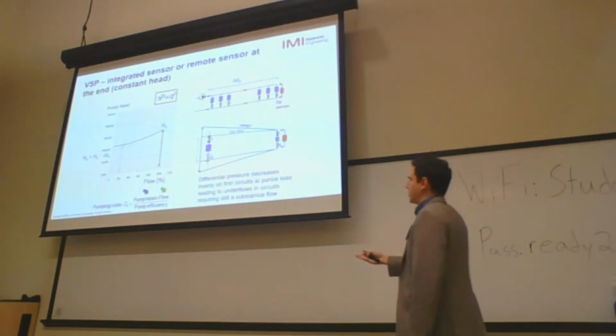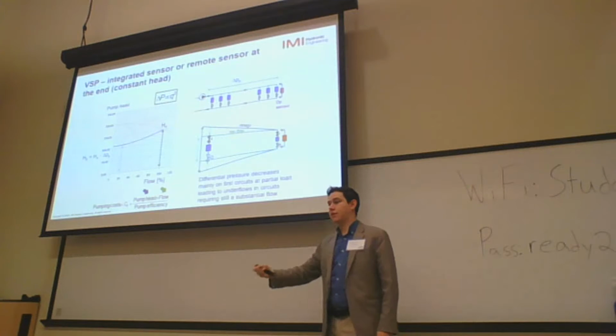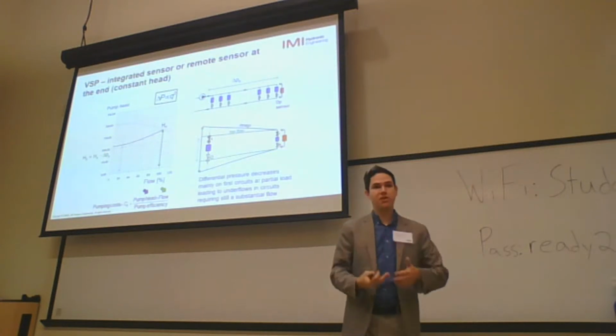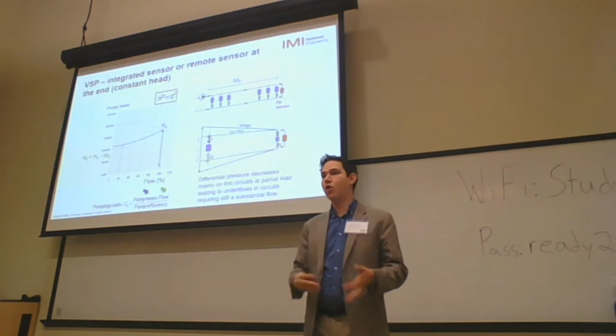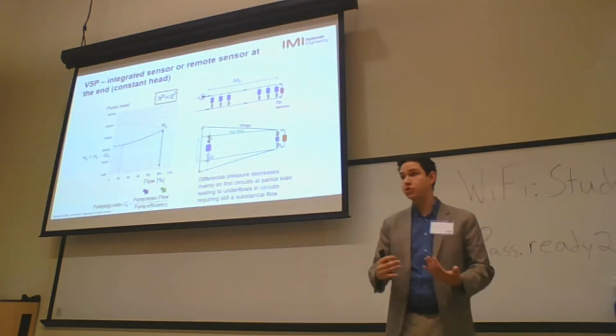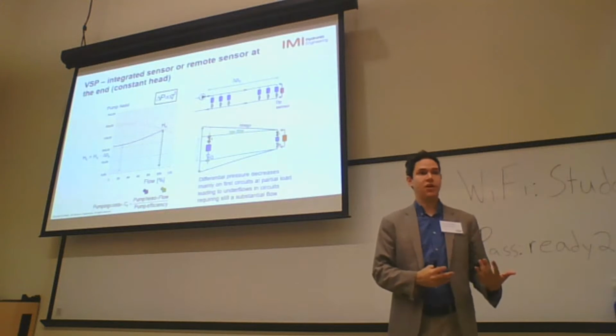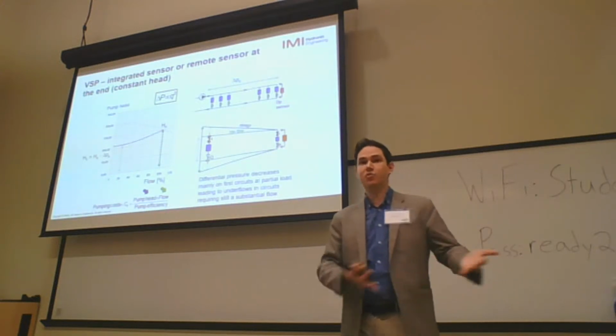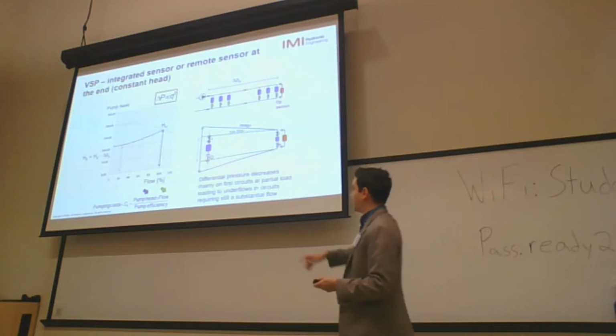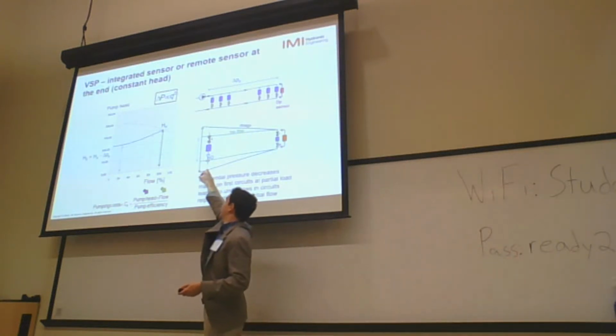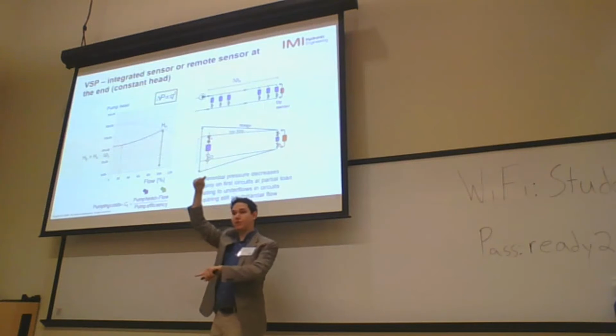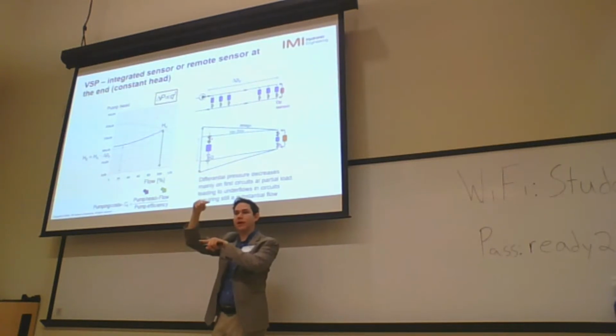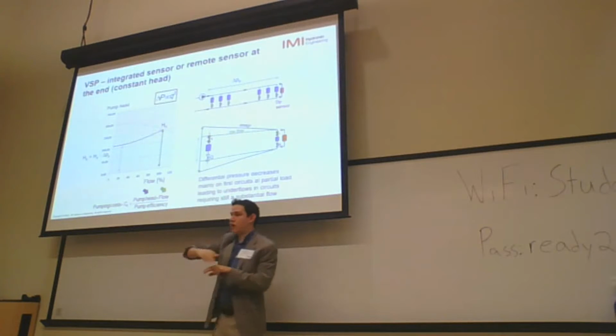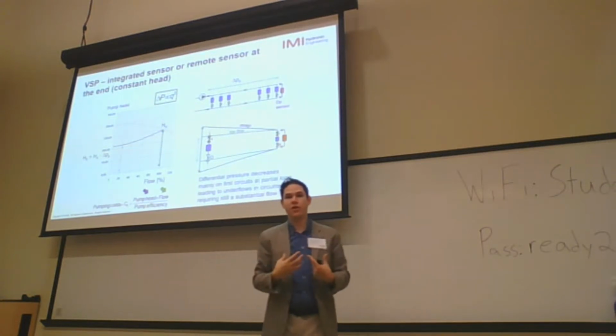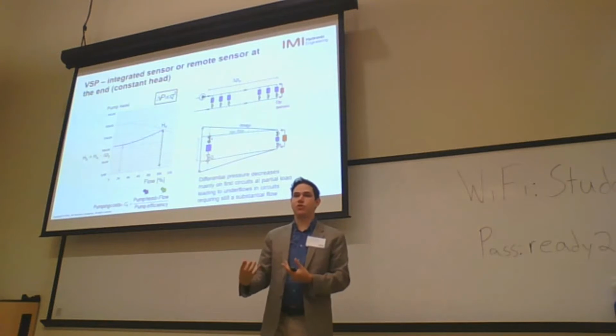So what happens in this scenario is, by placing a DP sensor on your index line or index coil, you're saving a lot of energy, but you may have the problem of not having enough water in some of your coils, even the ones closer to the pump, not having enough water to get the heat output that they need. When you look at this coil specifically, it needs between this black part and the top black part, so it needs a higher differential pressure, but it's only getting between the two green lines. So what's going on is this control valve is probably fully open, asking for more water, and the pump is not giving enough pressure.